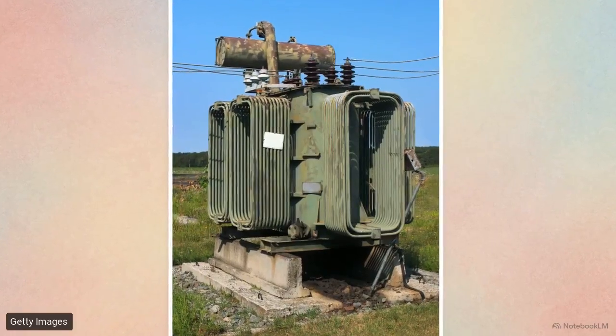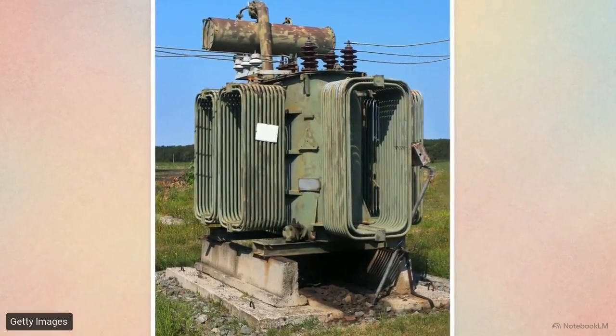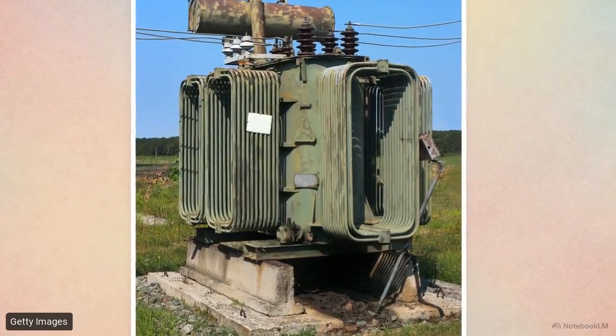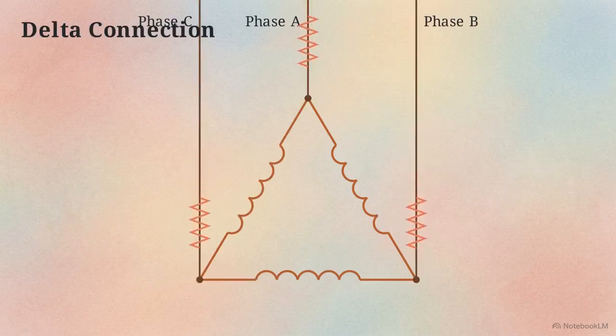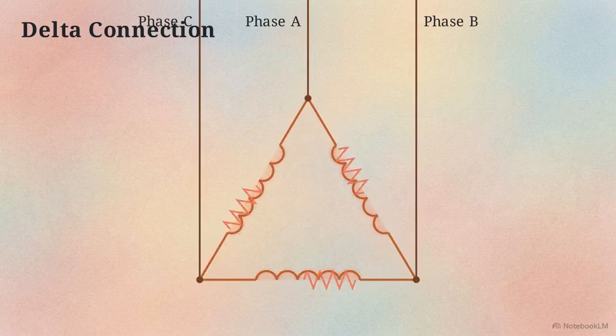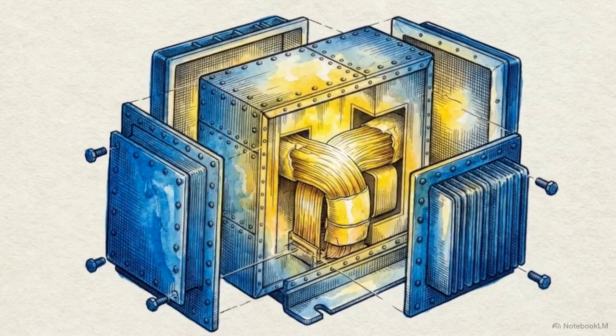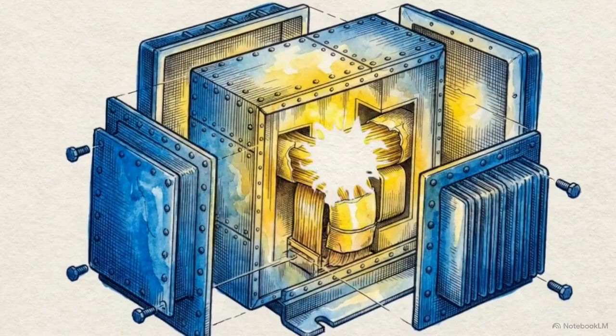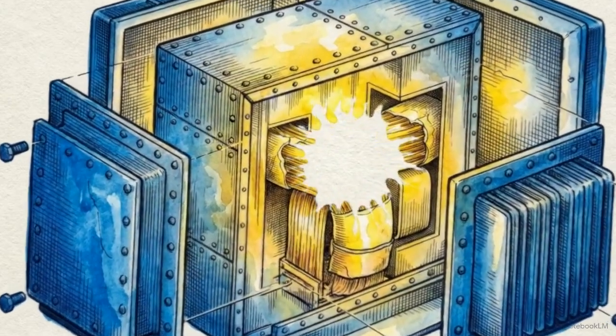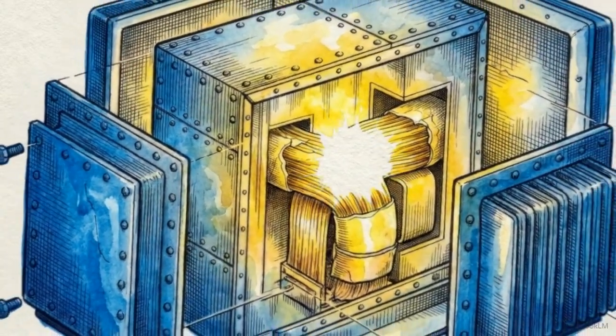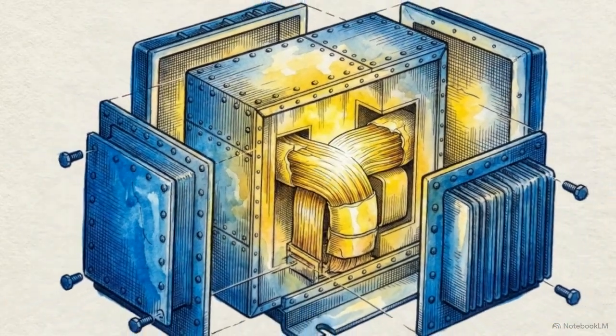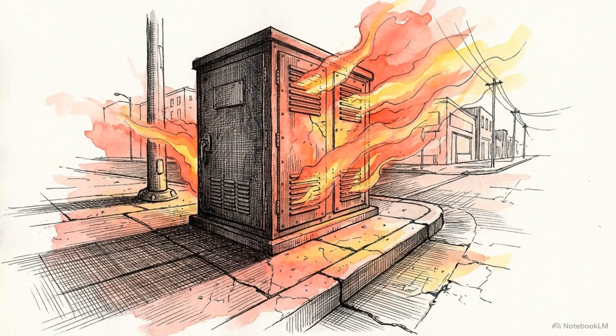The overload travels upstream from the building's wiring to launch a direct assault on the heavy distribution transformers. Triplens get physically trapped inside the specific triangular configuration of the transformer's copper coils, circulating endlessly in a closed loop. This trapped circulating current acts like a massive internal heating element. It cooks the wire insulation, slashing the hardware's lifespan from decades to mere months. Because of this invisible electrical noise, the grid quietly incinerates its own most expensive infrastructure from the inside out.